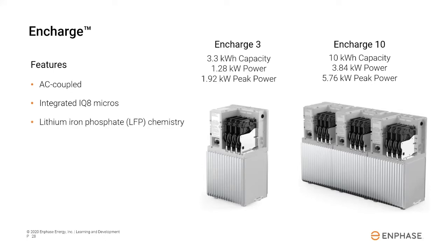The battery chemistry of the Encharge is lithium iron phosphate, or LFP, which is a safer and more stable lithium-based chemistry than typical lithium-ion batteries like NMC, or nickel manganese cobalt. Since LFP battery chemistry is inherently safer, the Encharge units have a passive cooling system with no moving parts like pumps or fans. No moving parts means fewer fail points compared to other systems on the market.